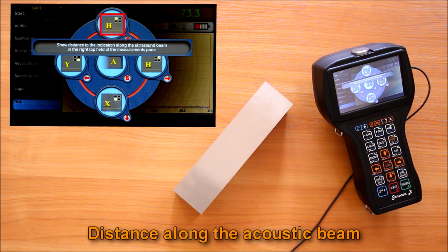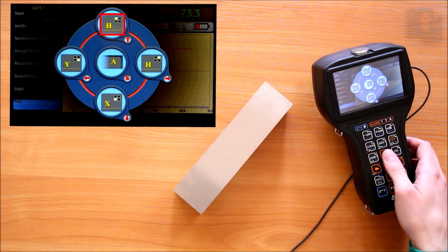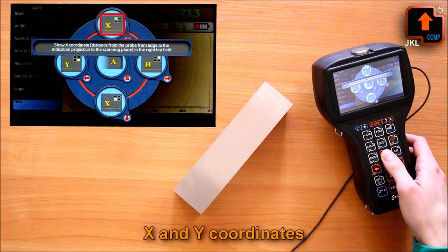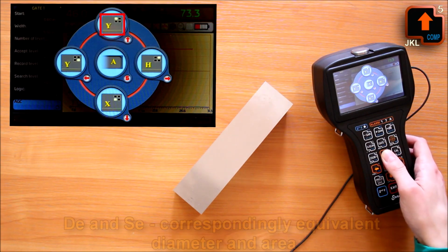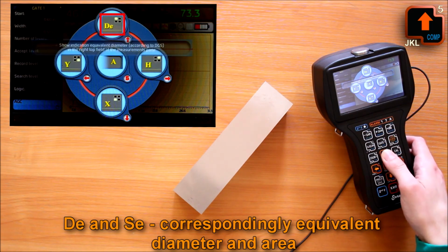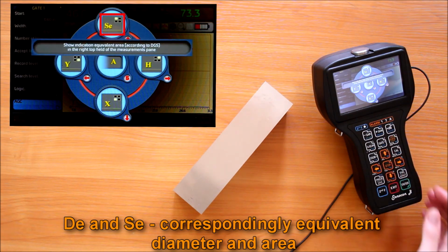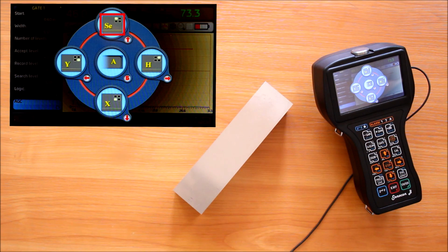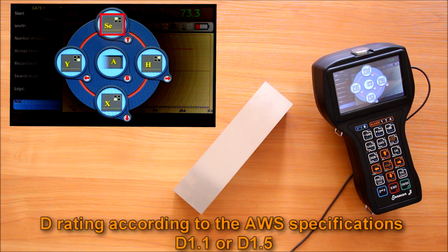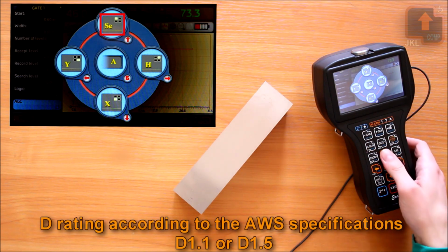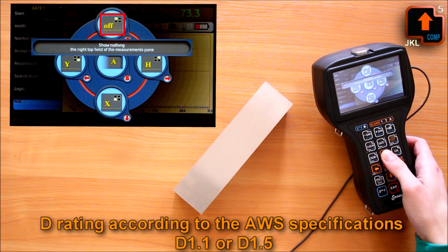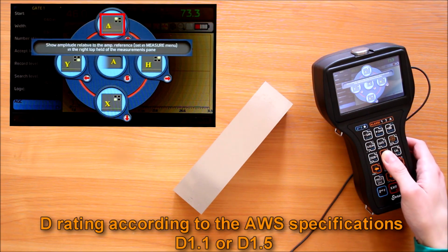distance along the acoustic beam, x and y coordinates, equivalent diameter and area available if TCG system is on, and D rating according to the AWS specifications D1.1 or D1.5 if it's on.